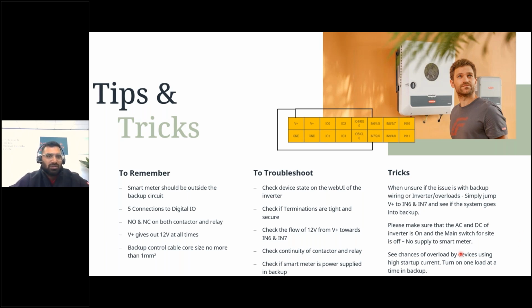Second thing to remember, there's just 5 connections at the digital I/O plug. We have V+ giving 12 volt. We have IO0 and ground power supplying the relay. We have IN6, which is the feedback from the contactor. We have IN7, which is the feedback from the relay. So if you have only done 4 connections on the digital I/O plug and are missing something, please double check the wiring.